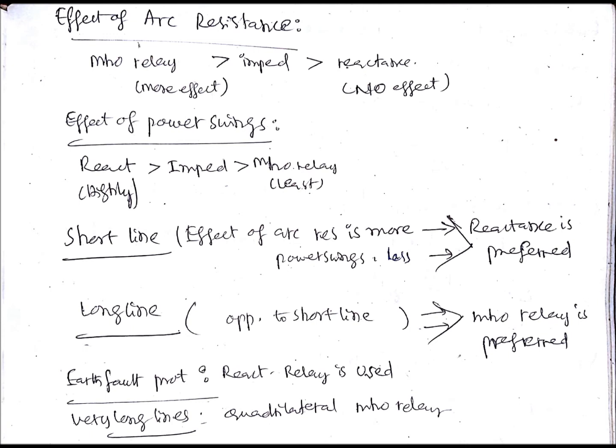The reactance relay will be preferred for short lines. One more reason is that the power swings will be very less in case of a short line because the power carrying capacity of a short line is less, so the power swings effect is also less. Now coming to the long line, you just think in the opposite way to short line.